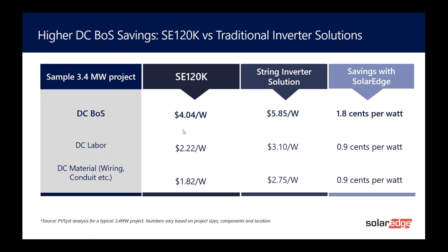As a result, we generally see a lot of savings on the DC side. If you have longer strings, you have fewer strings. Fewer strings means fewer home runs back to the inverter, and therefore you're saving all of that material and labor to install those wires. On this project, looking at the number of feet of wire we're saving, it was somewhere in the order of 8 miles of wire, so 40, 50,000 feet or more saved. I thought it was a good example of showing the benefit of using SolarEdge on ground mount projects.